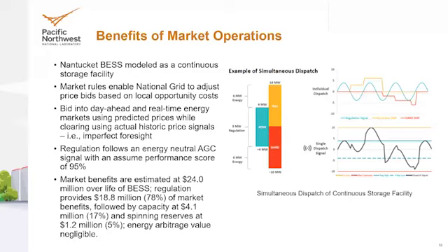You can see an energy-neutral AGC signal sent to the energy storage system, shown as that blue line regulating up and down across the zero axis. At times it's providing energy, shown by the yellowish line, and if it's discharging energy, there's a positive net flow onto the grid. At other times it's a demand-side resource because it's absorbing energy. You can see when those three signals are combined, the outcome shown in the lower right. It gets this very unique signal sent to it, and it's compensated accordingly. There's telemetry to ensure the energy storage system is actually providing all these services when asked to do so.